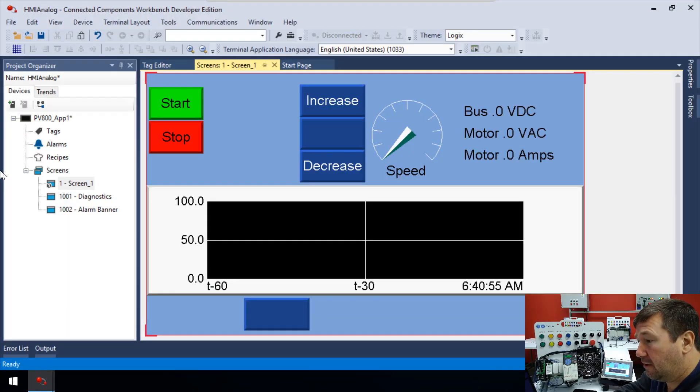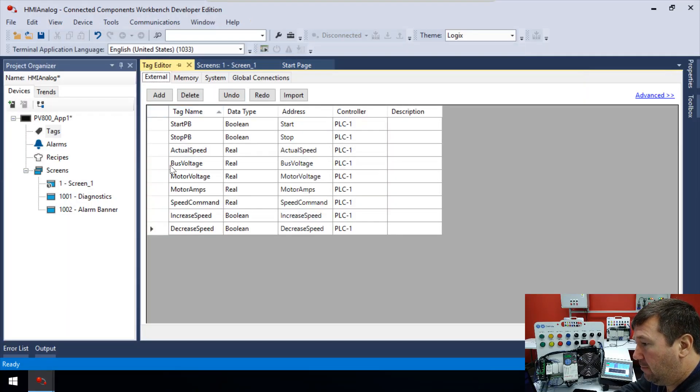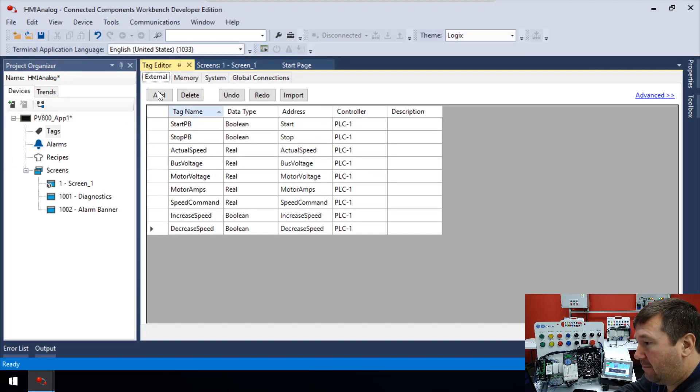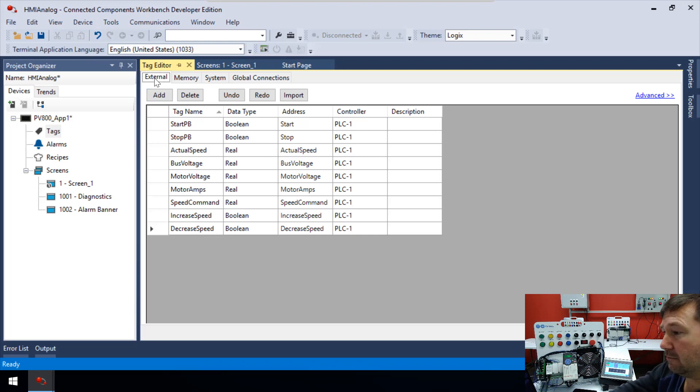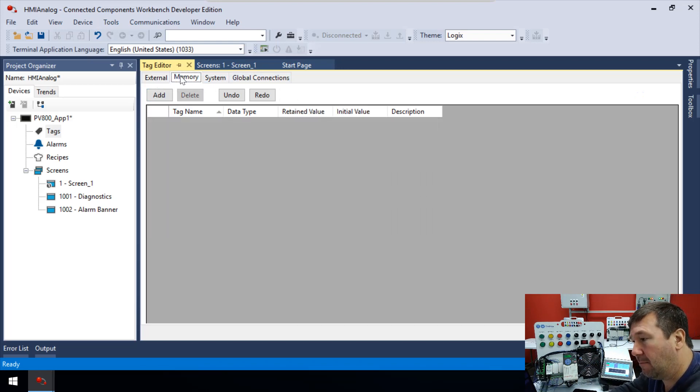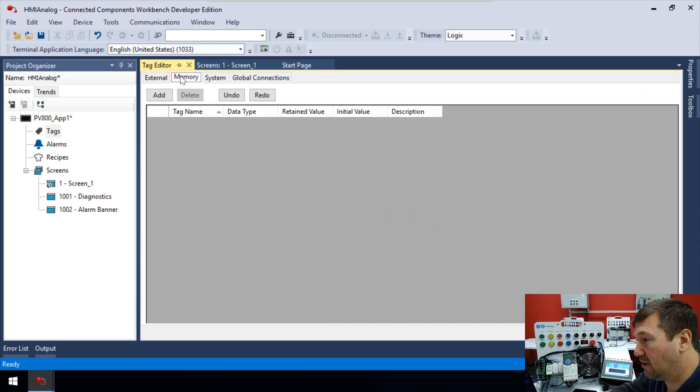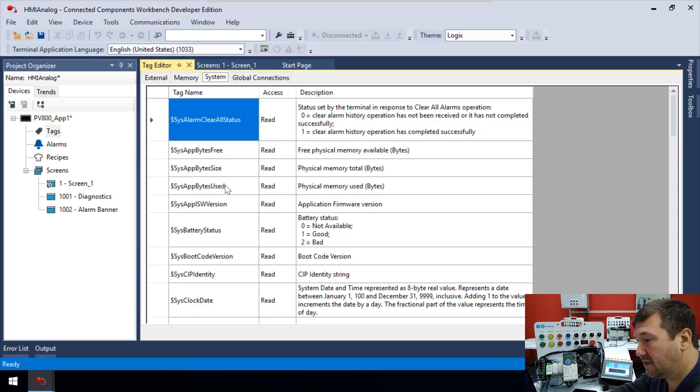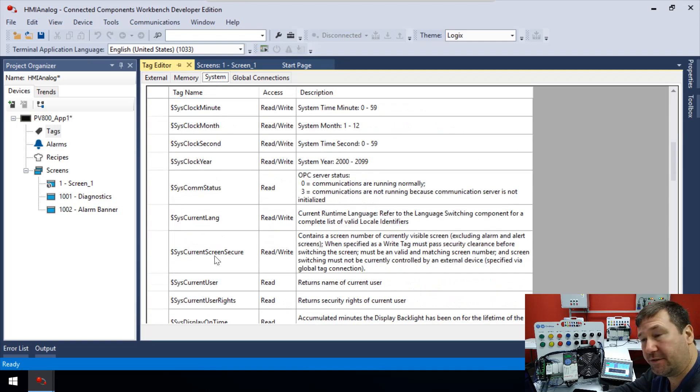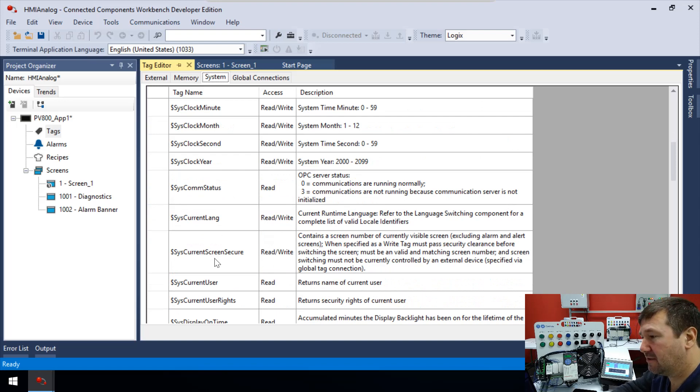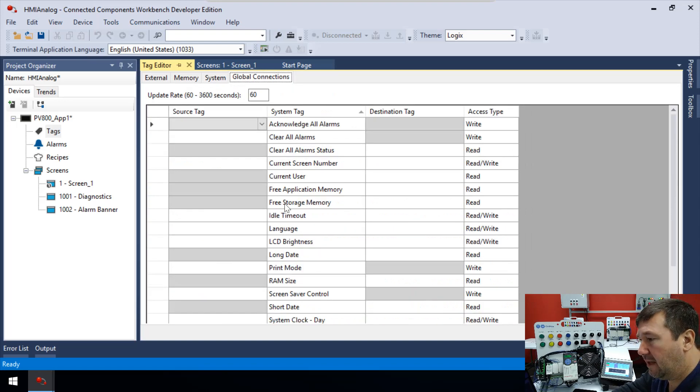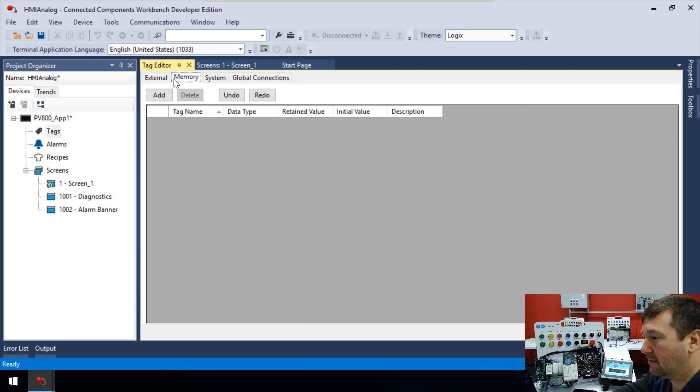Well, not all tags actually have to come from the PLC. You can also have internal tags. So what we're going to do is we're going to go back to our tag manager. And we've been working in the first tab here, which is the external tag. So that means things external to HMI that we're communicating with. But there's actually four tabs up here. So we have the memory tab, which is actually what we're going to use. We also have the system tab. And this gives you some information, mainly some status things that you can use in your program, such as the time, the current screen, and we may do some things with it later. And then we have global connections. And we are going to do a video on some of these. But right now, let's get back to that memory tab.